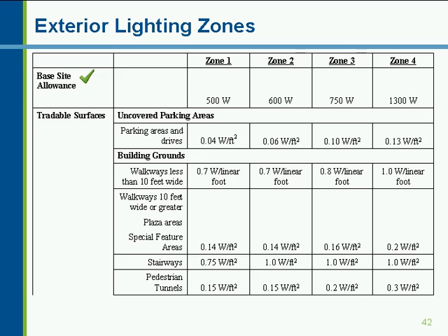The base allowance is there because there's a realization that if you have a small building, you're not going to be covered potentially by a lot of the allowances per square foot. You're going to have somewhat higher needs simply because of what's considered the economies of scale. You have a smaller building, you don't have as much square footage to get the wattage you might need. So you start off with a base allowance.